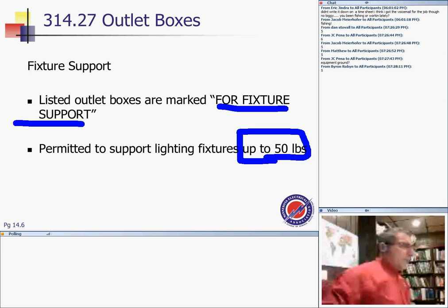up to and including 50 pounds. Matthew, my friend, if you have a fixture that's bigger than 50 pounds, then you hire your structural engineer, and you have to provide trusses for it, and you support it independently, independent of the box. So boxes used as luminaires or lamp holders shall be designed for the purpose and shall be marked to indicate the maximum weight of the fixture that's permitted to be supported by the box, other than 50 pounds. At every outlet used exclusively for this, the box shall be designed or installed so the luminaire may be attached to it.